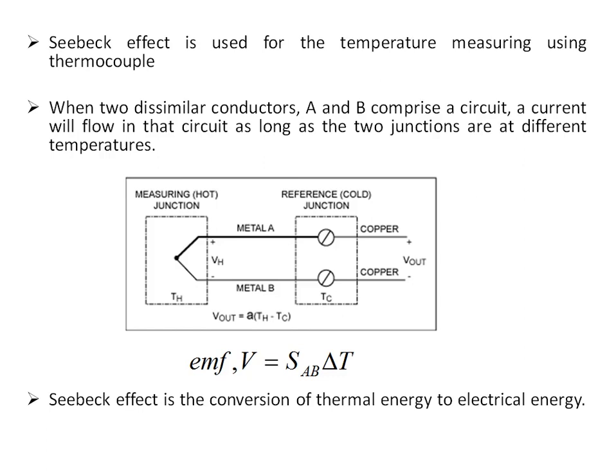The Seebeck effect is used for temperature measurement using the thermocouple, which is one of the commonly used devices. When two dissimilar conductors A and B form a circuit, a current will flow as long as the two junctions are at different temperatures. The EMF induced is directly proportional to the temperature difference, so by measuring the EMF, the temperature can be indirectly estimated. The Seebeck effect is essentially the conversion of thermal energy to electrical energy.